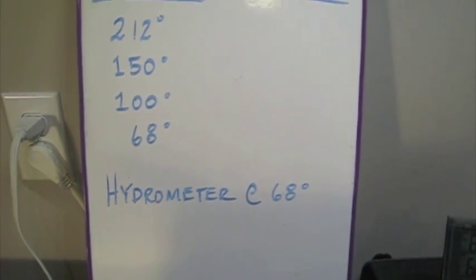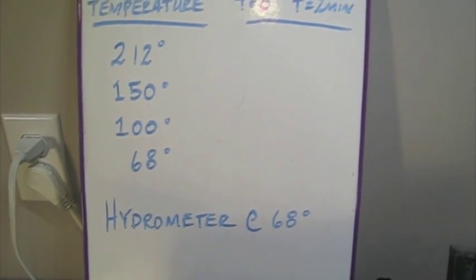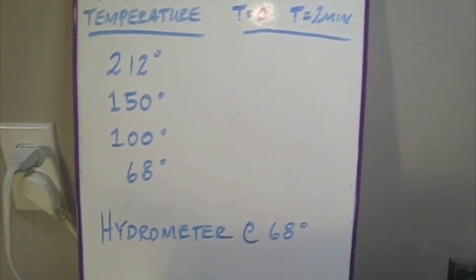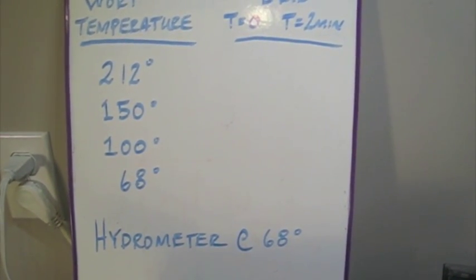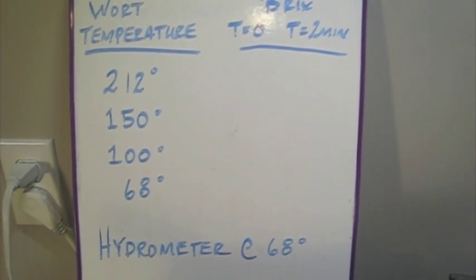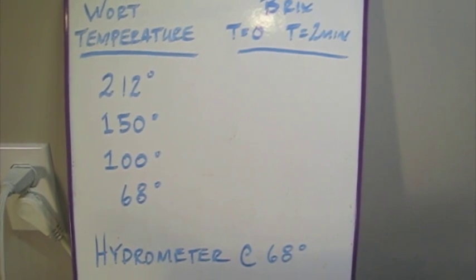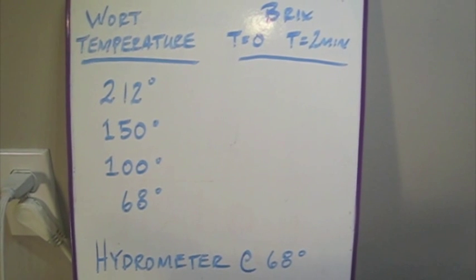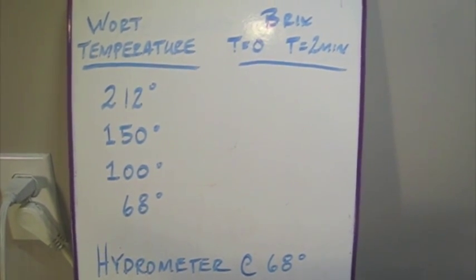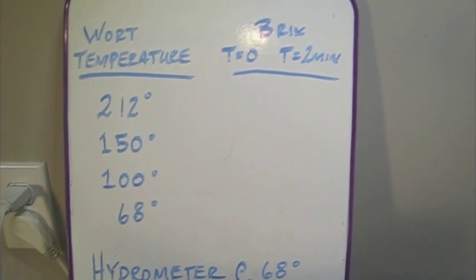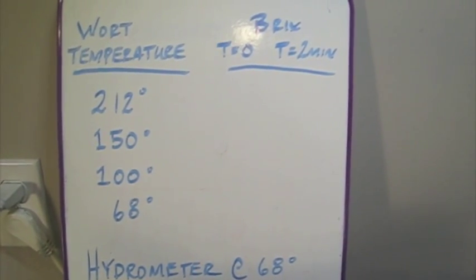So again, I'm looking at consistency of each sample right after the sample is taken and allowing it a little bit of time to cool to room temperature. Because I think oftentimes the problems we have with our refractometer is that even though the ATC is a feature listed, you really still need to have the ambient temperature and the sample at a stable temp.